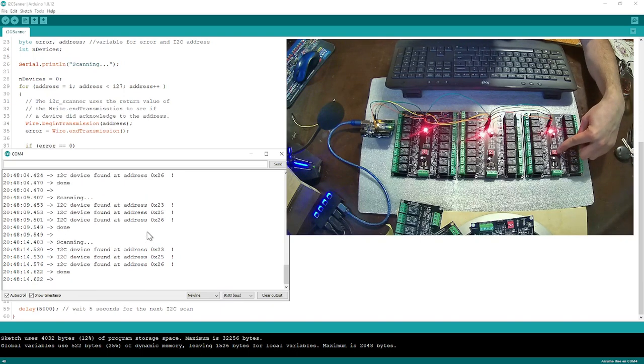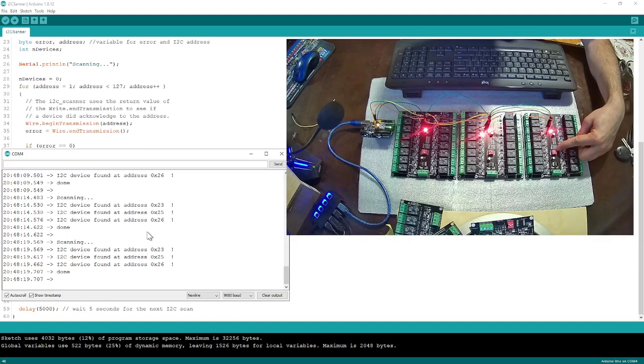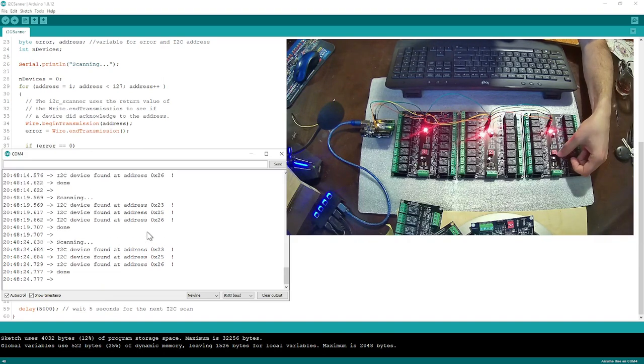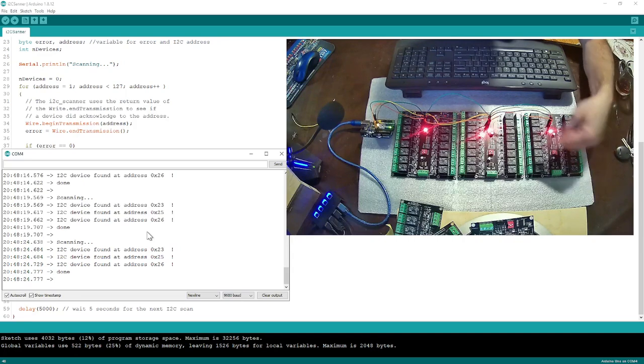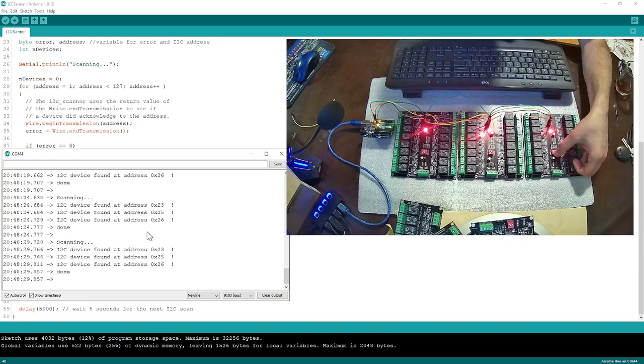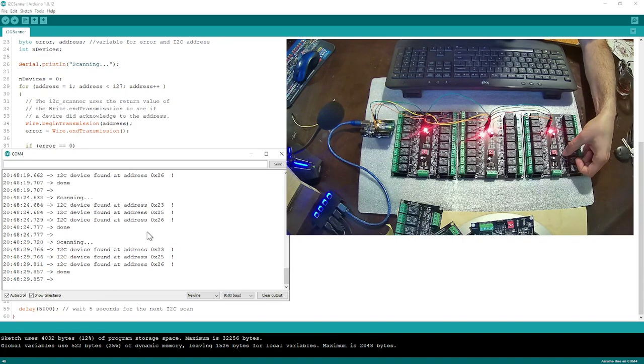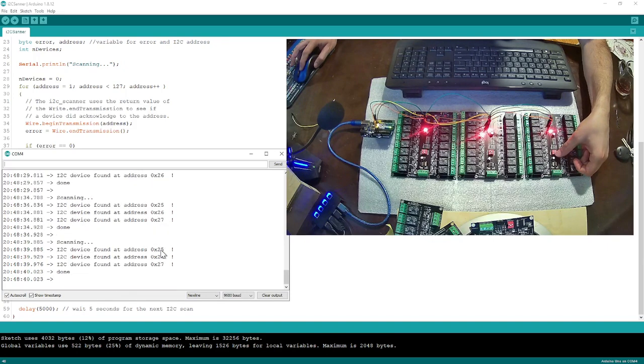I have numbers on the DIP switch — I'm not sure if you can see them, but number one is on the left, number two is in the middle, and number three is on the right. Number one is currently all the way down. I'm going to flip it up and see what changes. As you can see, it was 23 before and now it is 25. I'll put it back down — that is the second way to identify which board has which address.